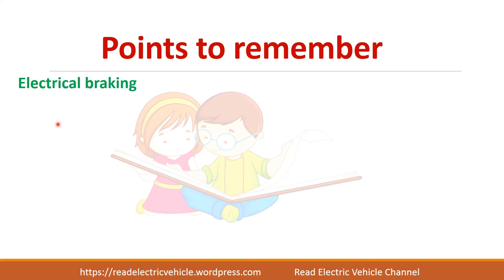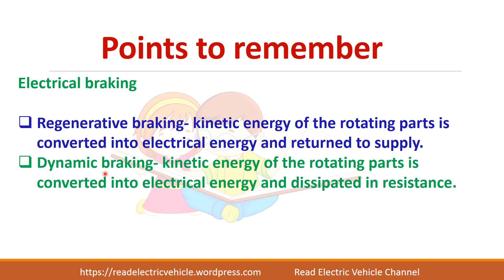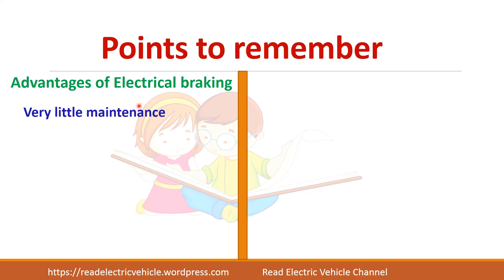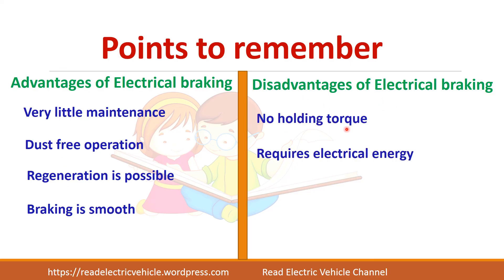To summarize: electrical braking systems are of three types — regenerative braking, dynamic braking, and plugging. In regenerative braking, the electrical energy is returned to the supply. In dynamic braking, it is dissipated in the resistance. In plugging, the armature connections are reversed to produce the braking torque. The advantages of electrical braking are: very little maintenance, dust-free operation, regeneration is possible, and smooth operation. The disadvantages are: no holding torque, and it requires electrical energy for operation.